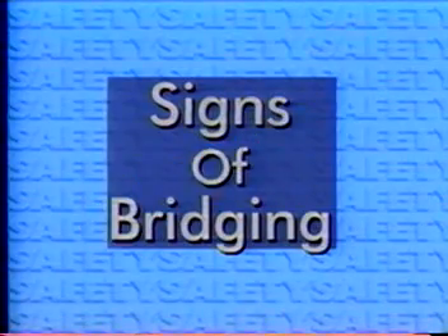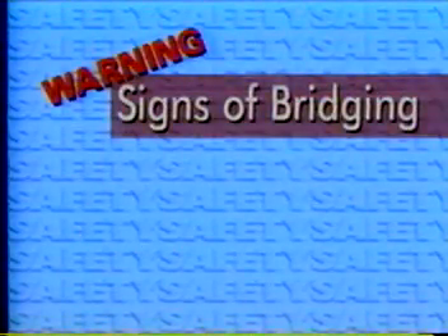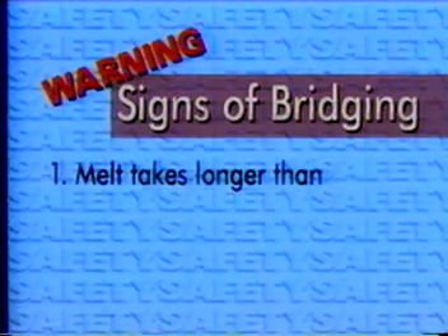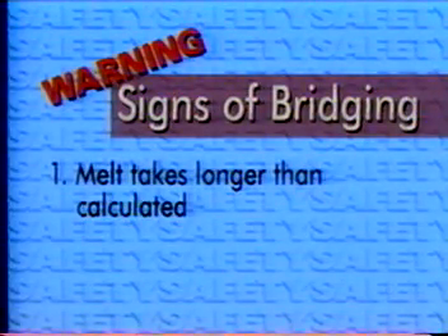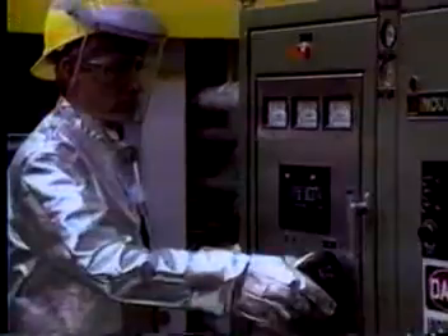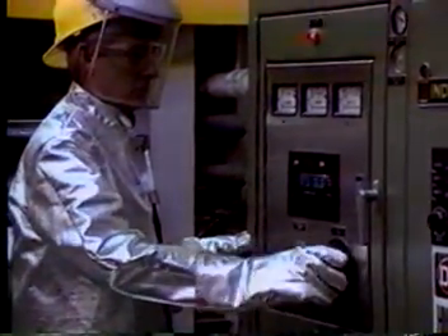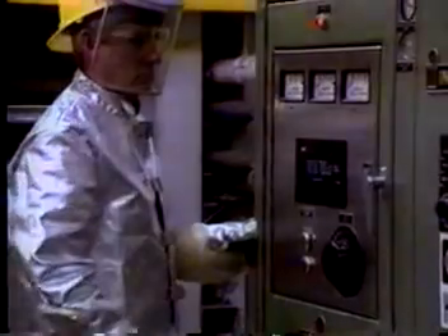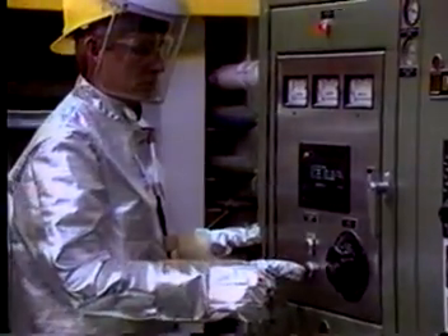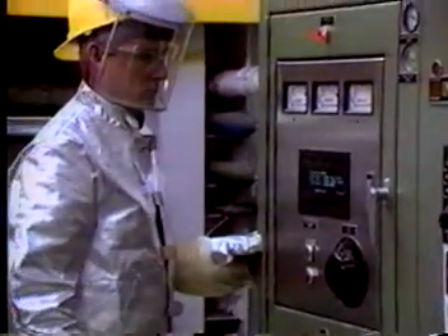Bridging may reveal itself with one of several warning signs. The most common and clear warning sign that bridging has occurred is that the melt is taking longer than calculated. If the charge is not melting down into the furnace as expected, or if there is solid metal in the top of the furnace when the operator would normally expect the bath to be fully molten, the operator must switch off power immediately. Under no circumstance should the operator increase power or extend melting time to try and melt that metal.